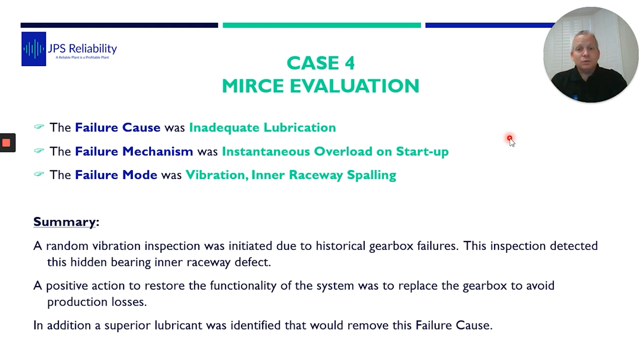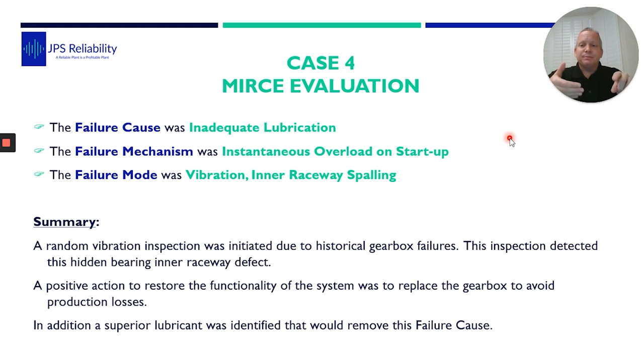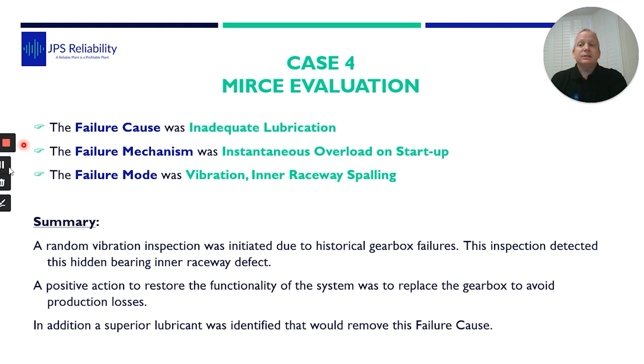The cause of failure was inadequate lubrication. The mechanism of failure was instantaneous overload on startup combined with inadequate lubrication. The failure detection mode was through vibration analysis, identifying an inner race spalling defect.